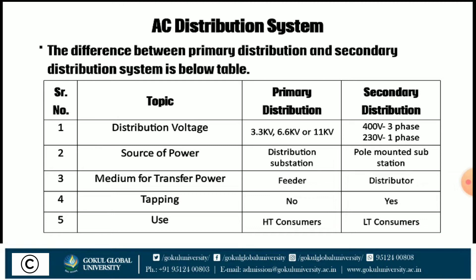In primary distribution, power is transferred by feeder, while in secondary distribution, power is transferred by the distributor. Regarding tapping: in primary distribution, no tappings are taken, while in secondary distribution, tappings are taken. Regarding use: primary distribution is generally used for HT consumers, while secondary distribution is used for LT consumers.